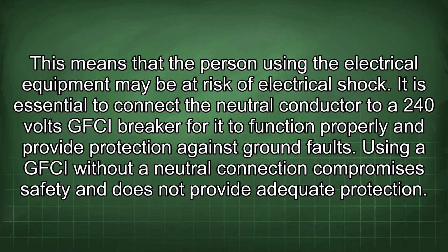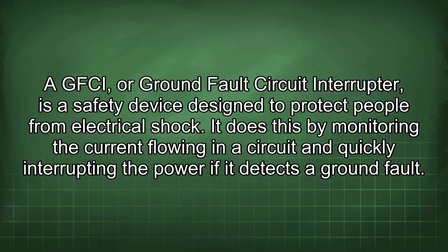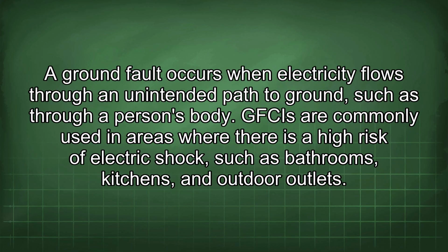It is essential to connect the neutral conductor to a 240 volts GFCI breaker for it to function properly and provide protection against ground faults. Using a GFCI without a neutral connection compromises safety and does not provide adequate protection. A GFCI, or ground fault circuit interrupter, is a safety device designed to protect people from electrical shock. It does this by monitoring the current flowing in a circuit and quickly interrupting the power if it detects a ground fault.